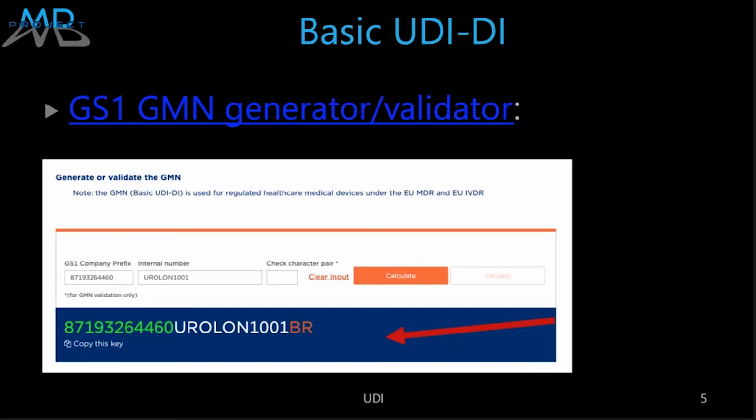So you don't really need to have 4 basic UDIs. That was my simplest way to tell them. That's absolutely correct. If it's just one tech doc, one DMR you have, and just different variations inside. Correct. Unless you change the intended scope, use, or design. Yeah, that's what I was about to say.